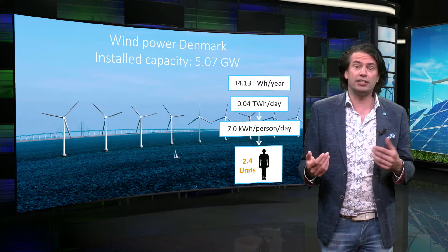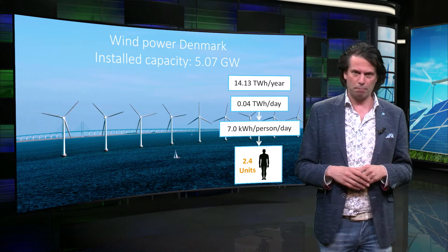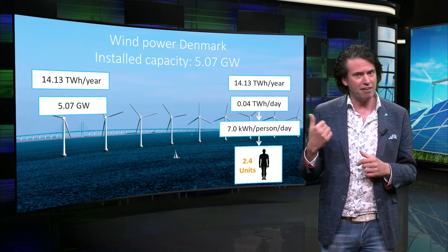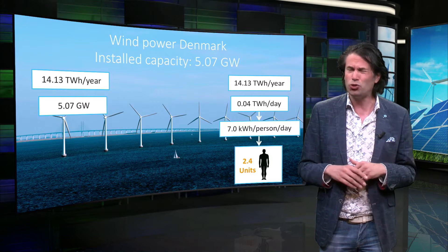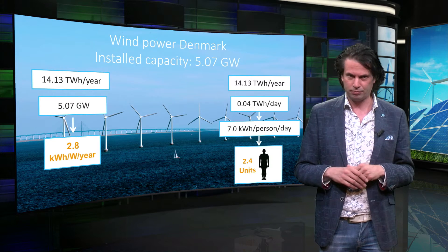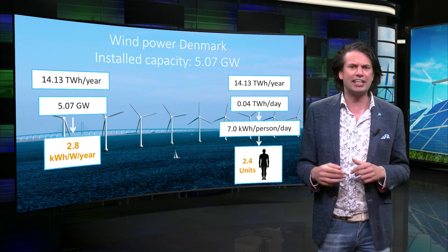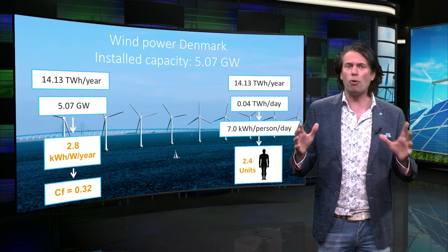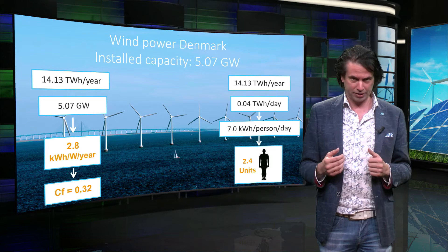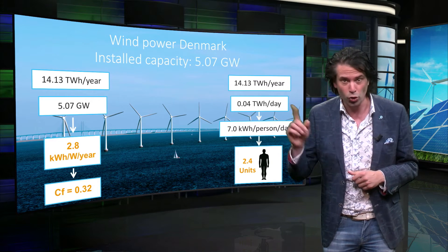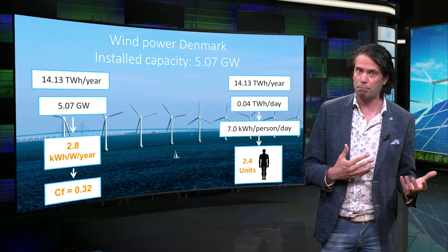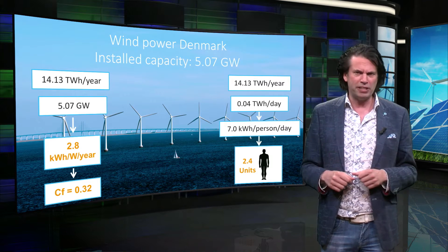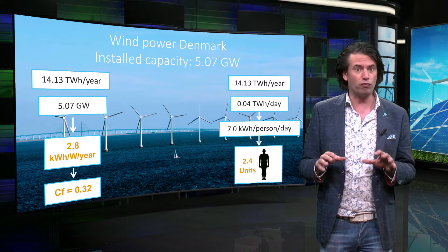We can calculate a value expressed in kWh per watt of installed capacity. In the case of Denmark, we divide the 14.1 TWh per year by the 5 GW of installed capacity to get about 2.8 kWh per watt of installed capacity. Dividing again by the hours in a year gives a capacity factor of 0.32. Comparing this with the capacity factor of hydroelectricity of around 70%, we conclude that wind energy produces less electricity per installed capacity unit than hydroelectricity. This is caused by daily and seasonal changes in wind speeds and because a wind turbine does not operate at maximum power for low wind speeds.